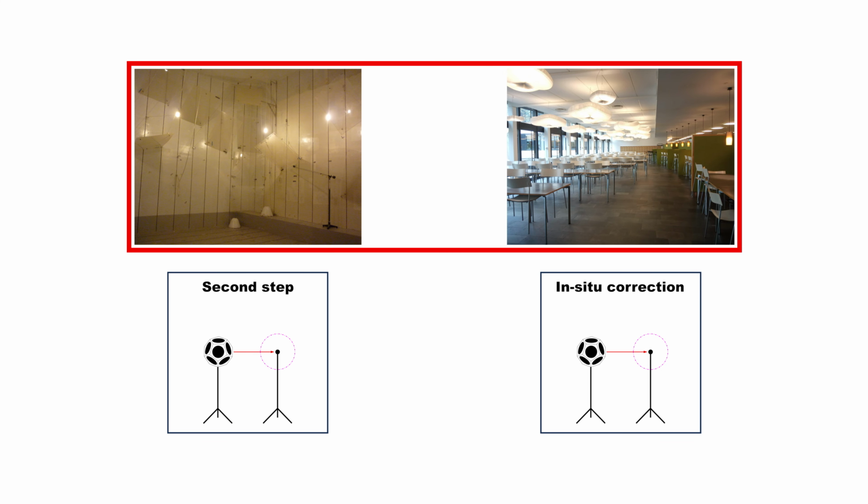For the diffuse-field calibration measurements in the reverberation chamber and the normal measurements at the measurement site, there are some guidelines you should follow. The height of the acoustic center of the source should be 1.5 meters above the floor. The height of the microphone should be 1.2 meters above the floor. Different microphone positions should be at least 2 meters apart.